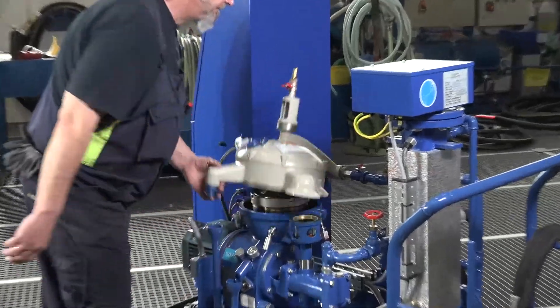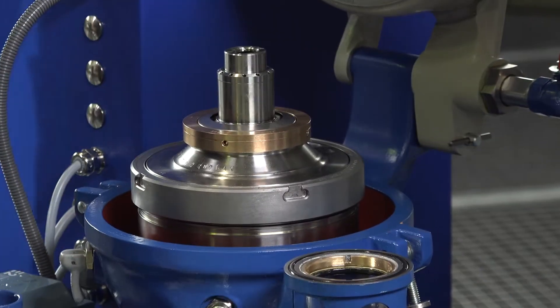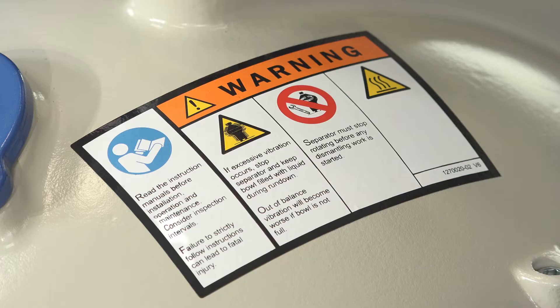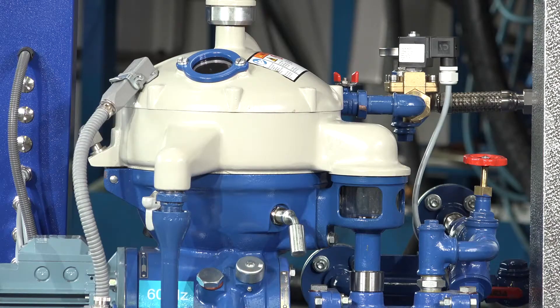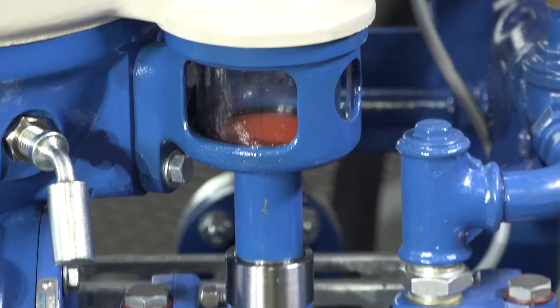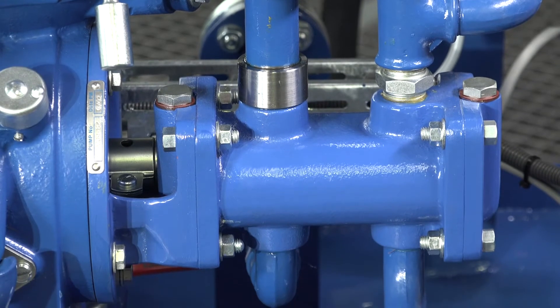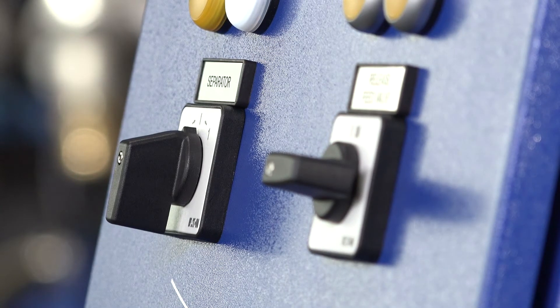When the separation temperature is reached, the heated lube oil is directed to the separator. In the high-speed separator, particles and water are separated from the lube oil by the force of gravity. The small OCM units operate with a built-on separator discharge pump for the cleaned lube oil outlet. Larger units work with a paring disc inside the separator instead of a discharge pump.